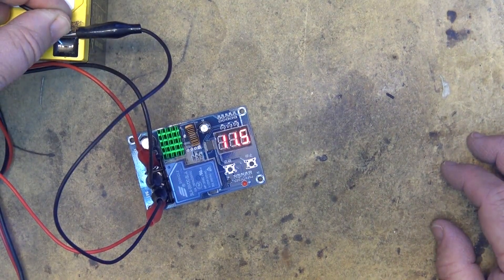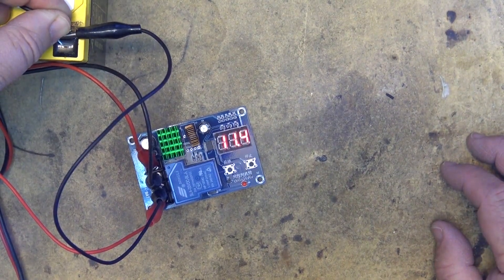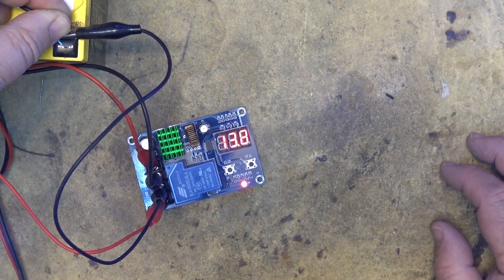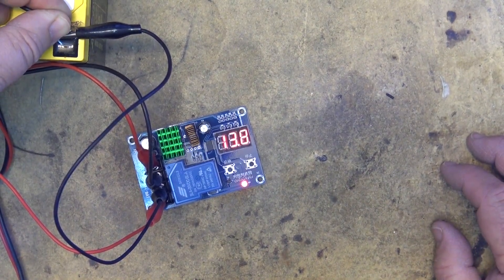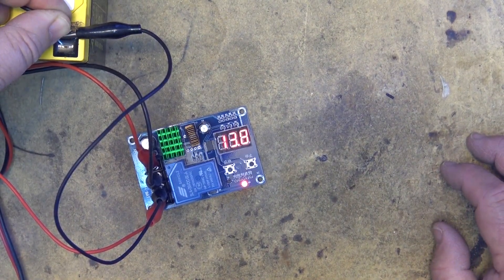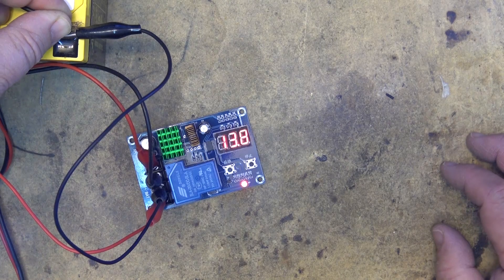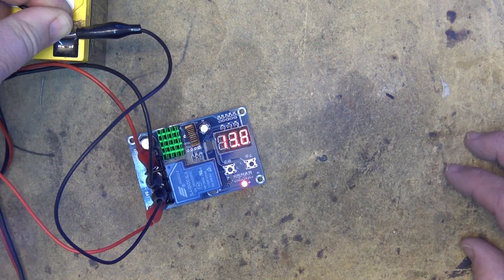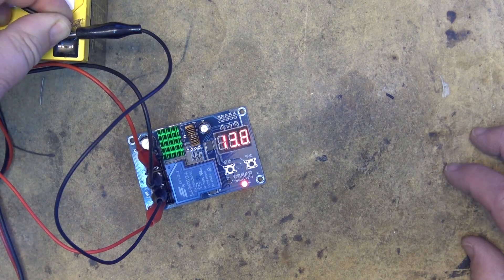One last test, I put the load on the battery, and again once the battery voltage drops, the charger will come on, and it will stay on until the battery reaches the high set voltage.